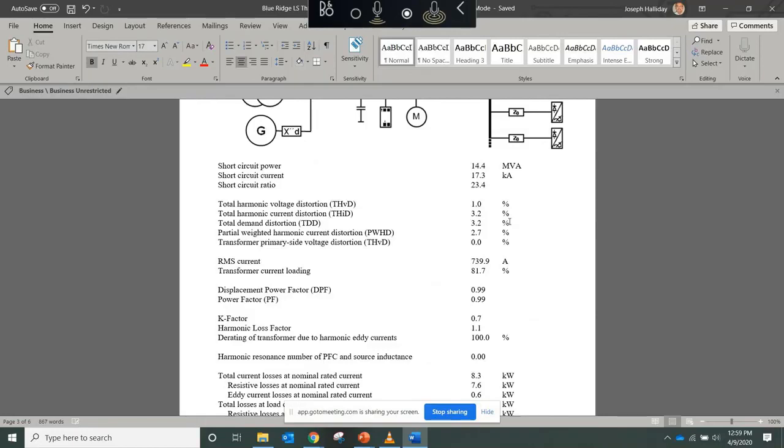And I look at, has anybody measured the motor lately? Has it been rewound lately? Has it been on a drive and you're retrofitting from an old drive to a new drive? Those kind of questions come up. But when it comes to transformer stuff, we simply look at transformer data.